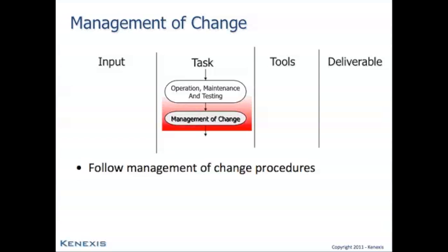But again, it's also important to remember that a new or separate management of change system that's dedicated to the fire and gas system or to safety instrumentation in general is not appropriate. It is important to have one single unified management of change system that applies to all process changes, and making sure that that system adequately addresses the needs of fire and gas detection and suppression equipment.